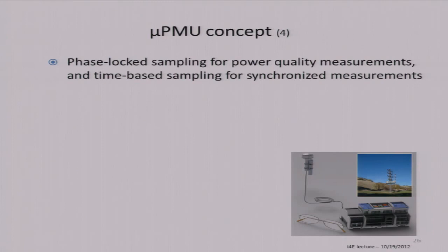But the frequency changes all the time. So your sampling algorithm has to track the frequency of the grid so that you always get, let's say, 512 samples per cycle. You have to be tweaking it up and down constantly.